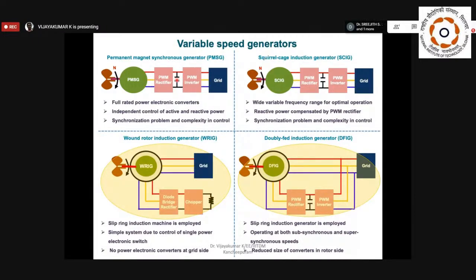So what I want to convey from these 2 topologies is, if you look at the power converter ratings, this power converter rating should be equal to the machine rating. If I say a 5 megawatt turbine, I can use a 5 MVA rating of the generator. You have 2 converters, so this converter rating also should be 5 MVA, because whatever power is generated in the generator can be channeled through these PWM converters, right? So your converter rating will be equal to the machine rating.